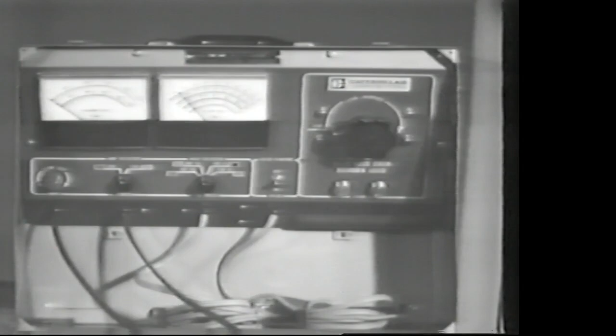This time we get voltage at the relay. We can check beyond the relay at the glow plug. It is also getting voltage. This test does not tell us that the glow plug is working, however. We can use the electrical tester to test the current drawn by the plug.